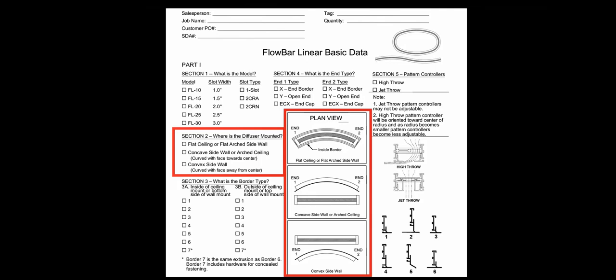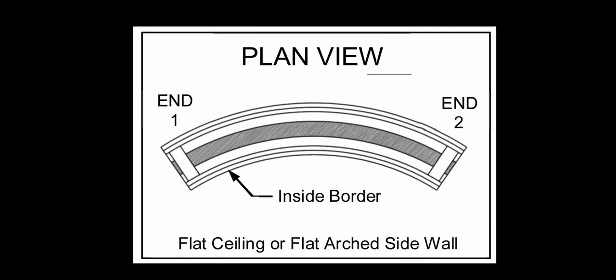Plan view, primarily for ceiling mounting, and concave or convex for sidewall or arched ceiling mounting. If the diffuser is to be mounted in a ceiling, or is a floor mounted CT bar grill, the representation of the product is shown in the plan view orientation. This is particularly important if the unit is not symmetrical or if each end fabrication is different.